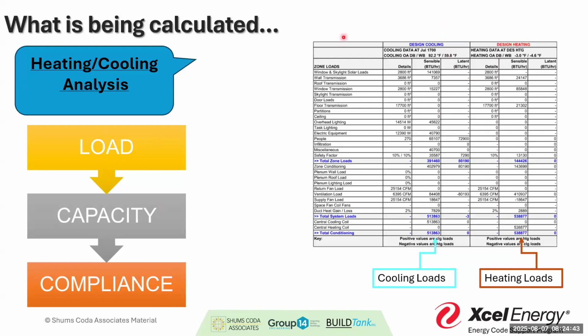When I start looking at a load calculation, I'm looking for certain elements like my design criteria to make sure it reflects the appropriate outdoor temperatures. I've seen some that have been set 1 or 2 degrees off, but I've also seen projects where they come in way off. I've got one that was in Minnesota - it was 17 degrees off on that cooling load.